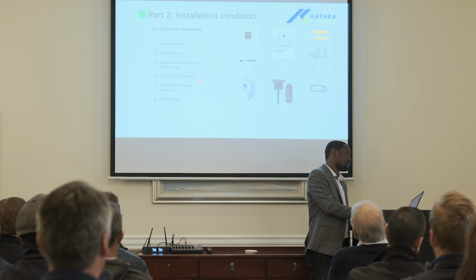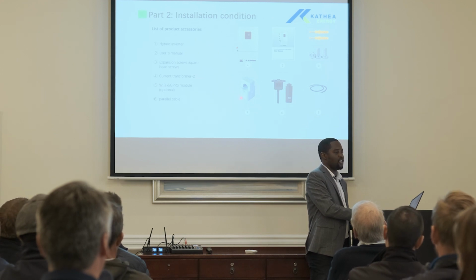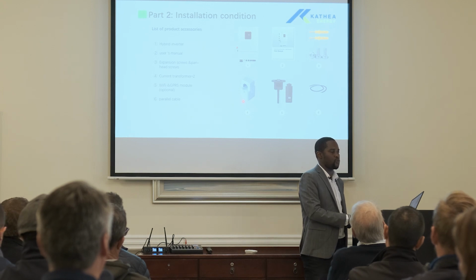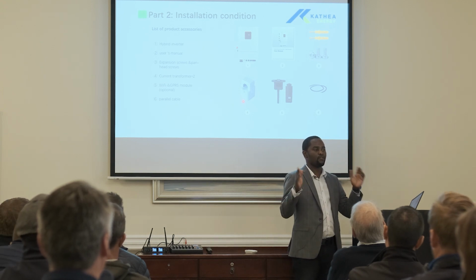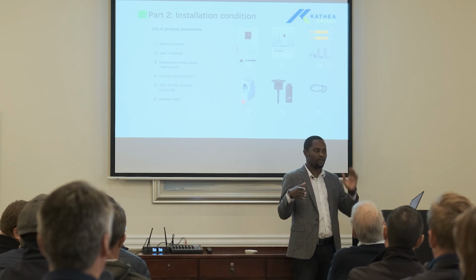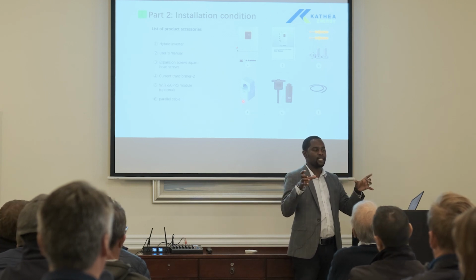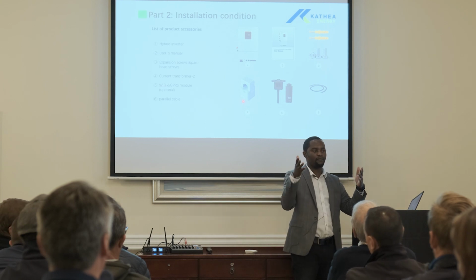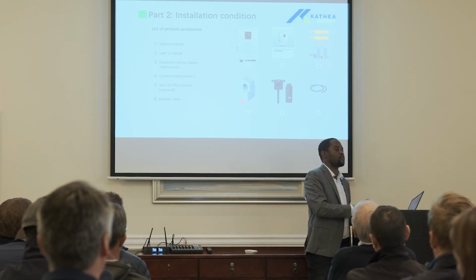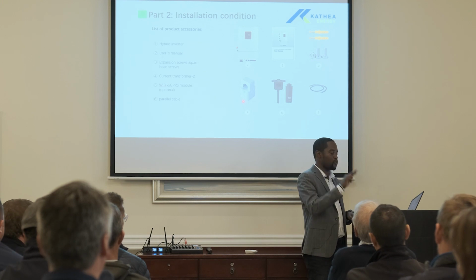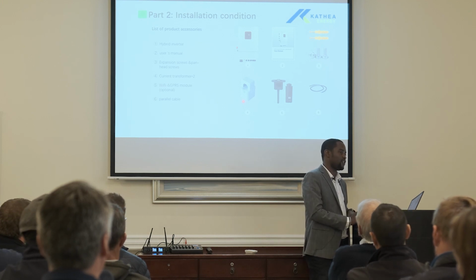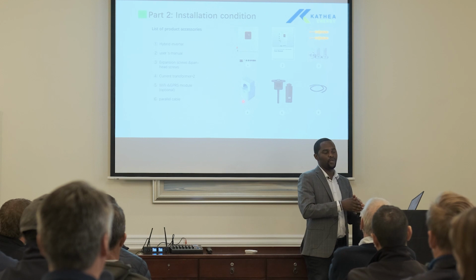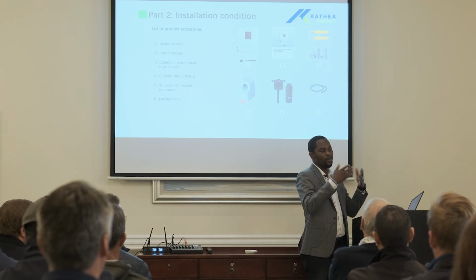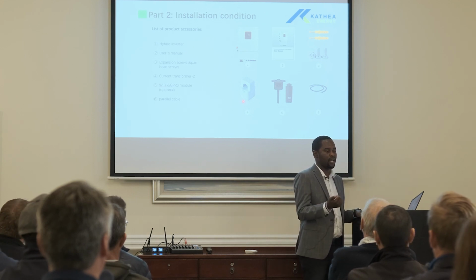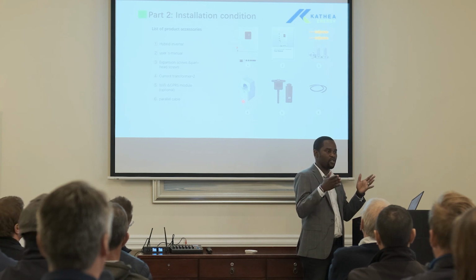I hope no one's going to ask why we've got two. So we actually have two because in future, they want this inverter to be able to integrate two grids. Let's say we've got two feeders. Let's say it's very critical. Then you've got feeder A and feeder B. They are in redundance. Then the inverter should be able to use either of those and be able to do the export control on each. That's why I've got two CTs and two CT slots. Currently, it's not activated. You can only use one grid input, which is the 100% scenario for all the houses that we have normally. But let's say it's a surgery where you can't afford any power outage.